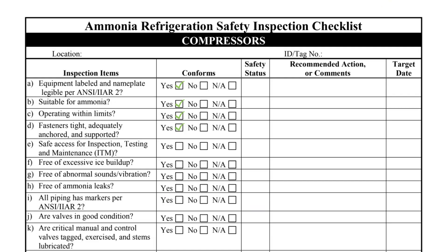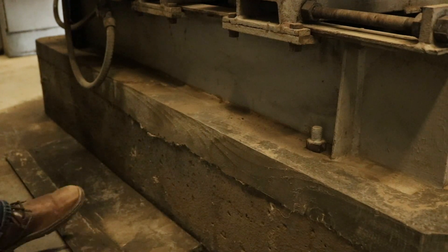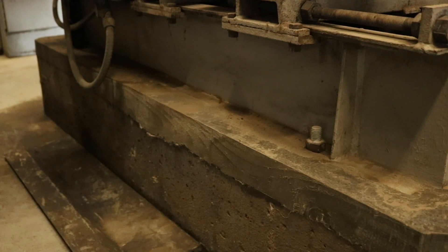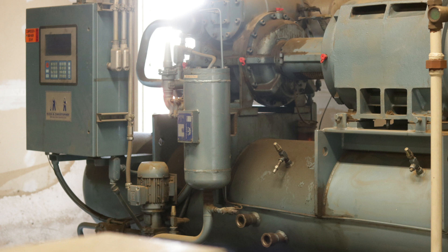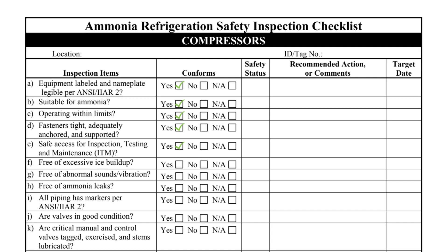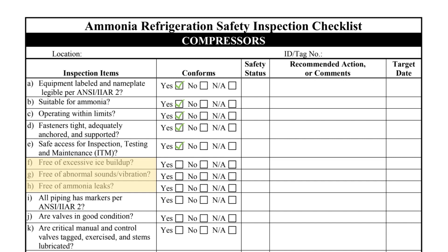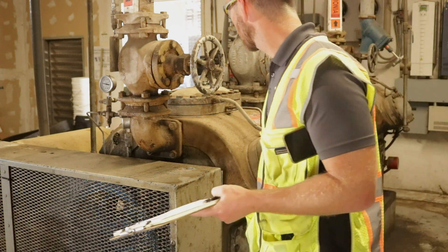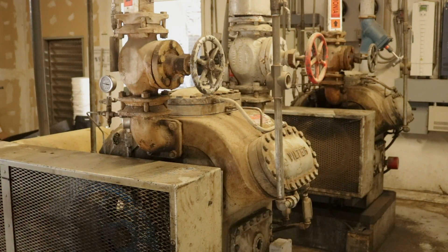Item D requires the inspector to verify that supports and anchorage are adequate; the anchorage should be inspected to ensure nuts are tight and free from corrosion. The compressor should have safe access for normal service and maintenance — this screw compressor is compliant in that regard. The inspector must do a visual inspection of the entire compressor to verify the equipment is free from excessive ice buildup, vibration, and leaks, inspecting from all sides where possible to avoid missing a deficiency.